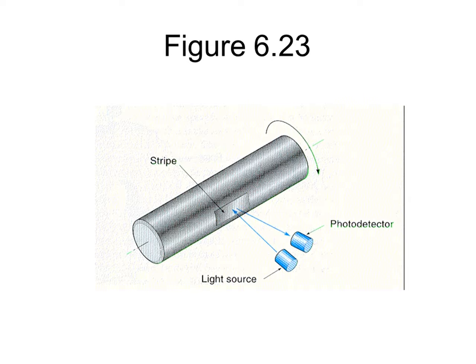This is kind of like an incremental encoder, that's exactly what it's like. But we usually only have one strip of tape, and we point the tach at the tape. It reflects the light back when it comes around, gets a real good reflection, and the instrument uses that to give us the speed.